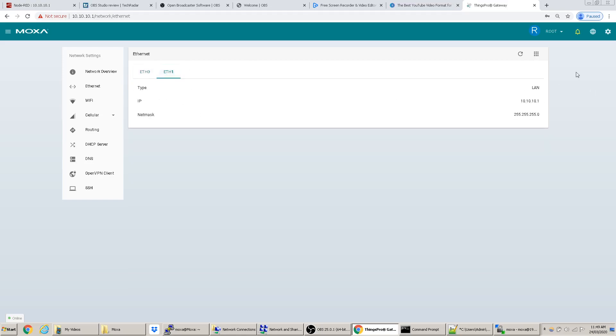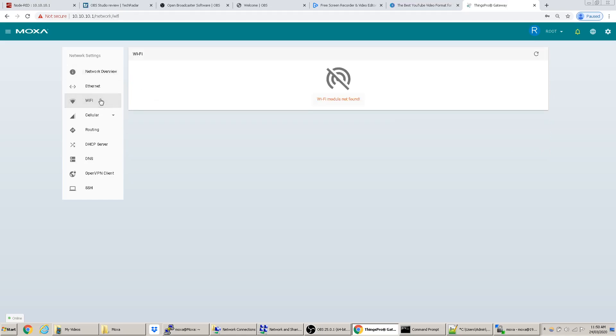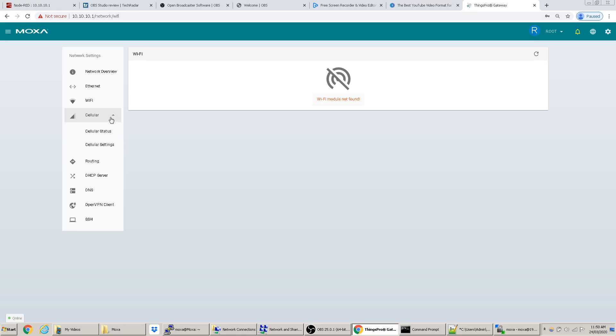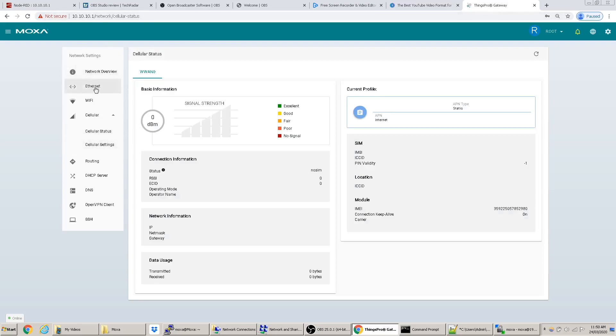You can go into settings and change the IP address as needed. There's no Wi-Fi module in this Moxa — you can get one, but you can only have either a cellular module or a Wi-Fi module. You can plug directly into the ethernet port for internet access as long as the port is set to DHCP.